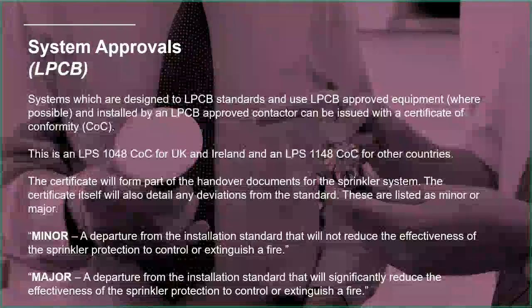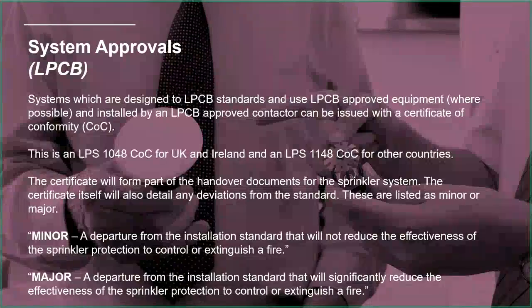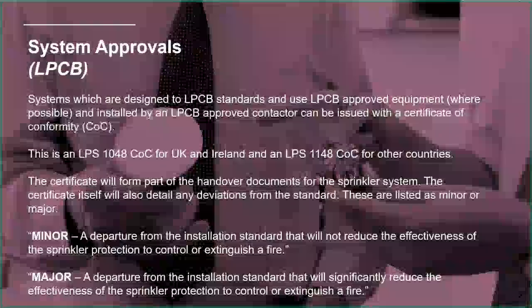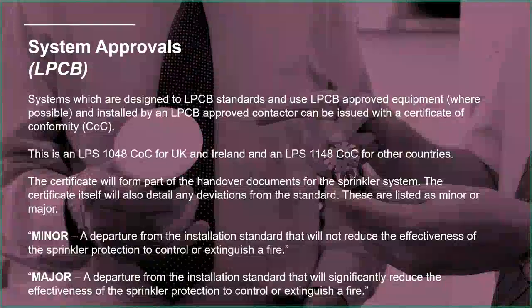A minor non-conformity means a departure from the installation standard that will not reduce the effectiveness of the sprinkler protection to control or extinguish a fire. That's recognising that the standard gives you an ideal world, but we don't live in an ideal world, and there may be instances where departing from the standard is just necessary to achieve the end result.